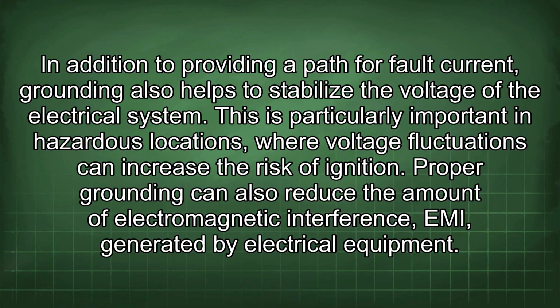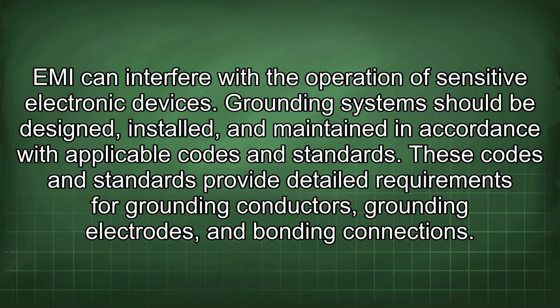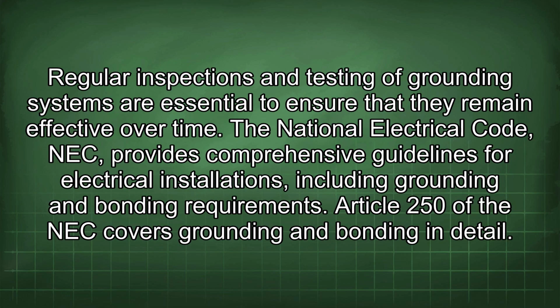Proper grounding can also reduce the amount of electromagnetic interference, EMI, generated by electrical equipment. EMI can interfere with the operation of sensitive electronic devices. Grounding systems should be designed, installed, and maintained in accordance with applicable codes and standards. These codes and standards provide detailed requirements for grounding conductors, grounding electrodes, and bonding connections. Regular inspections and testing of grounding systems are essential to ensure that they remain effective over time.